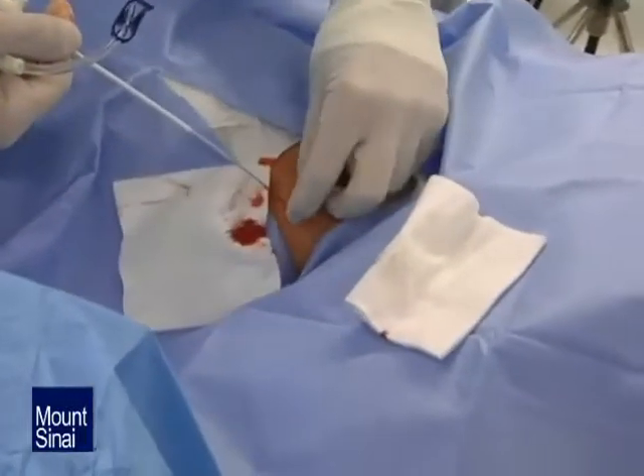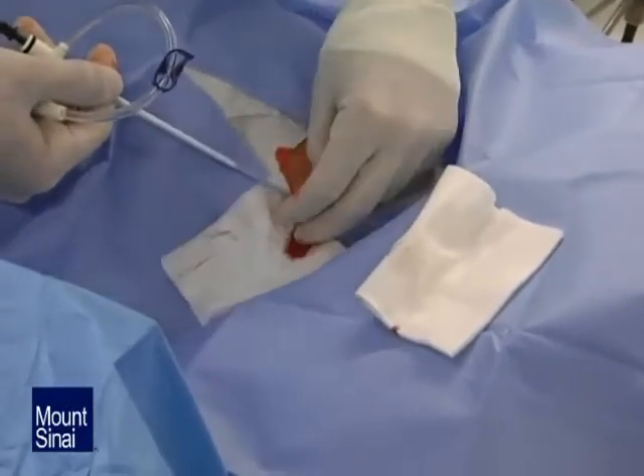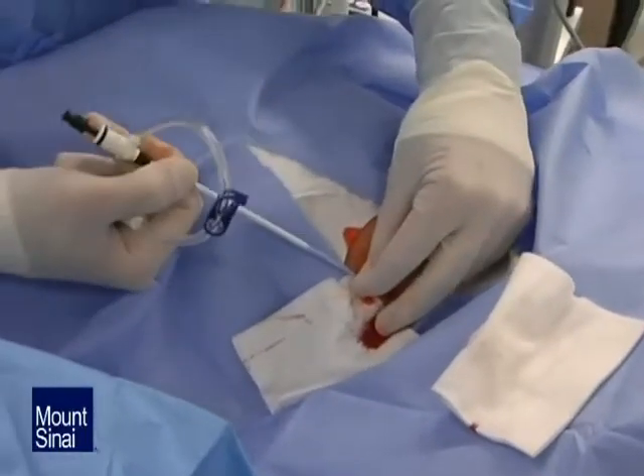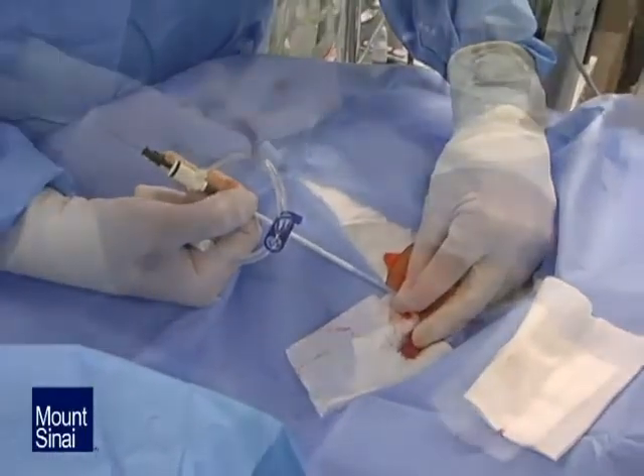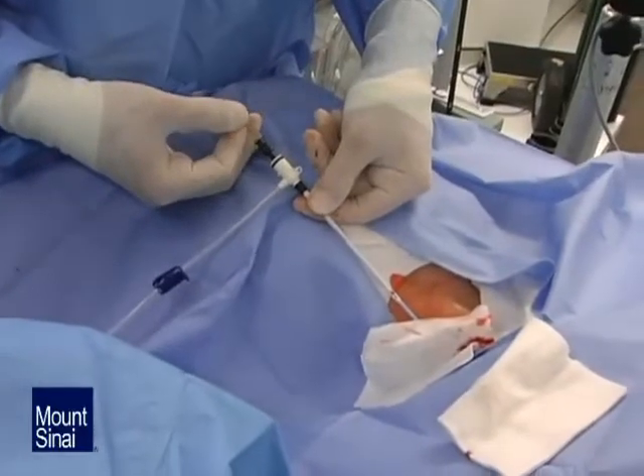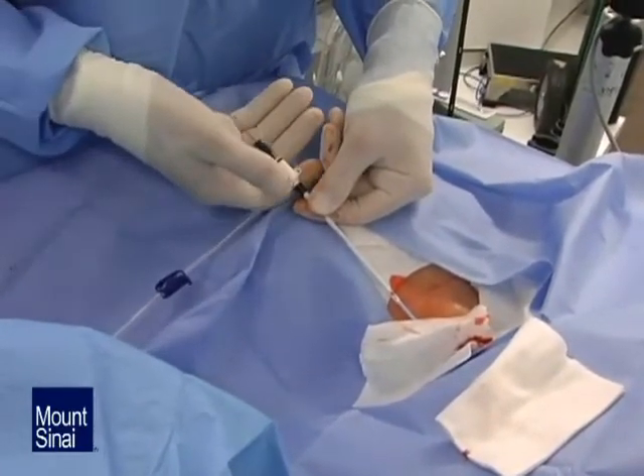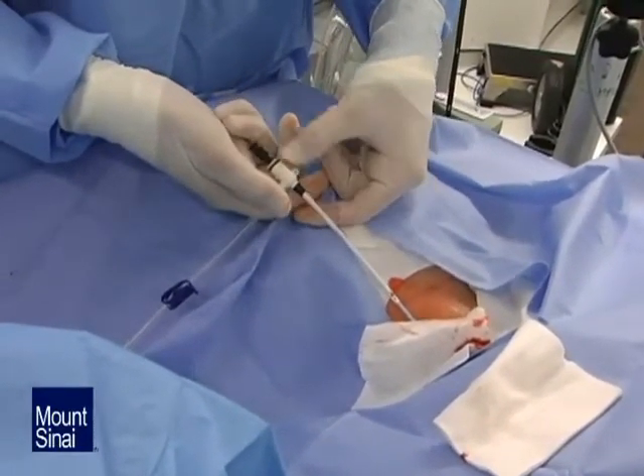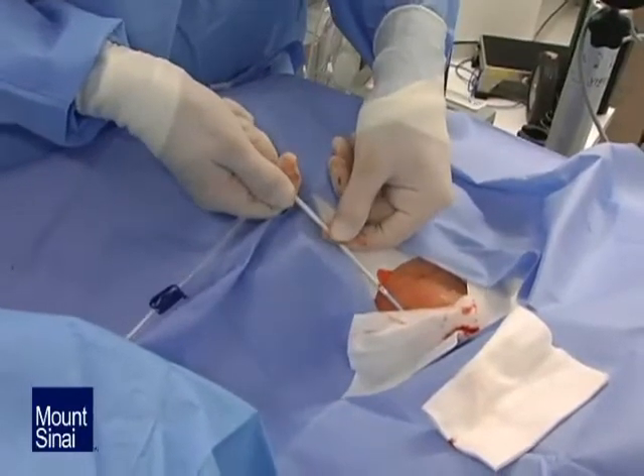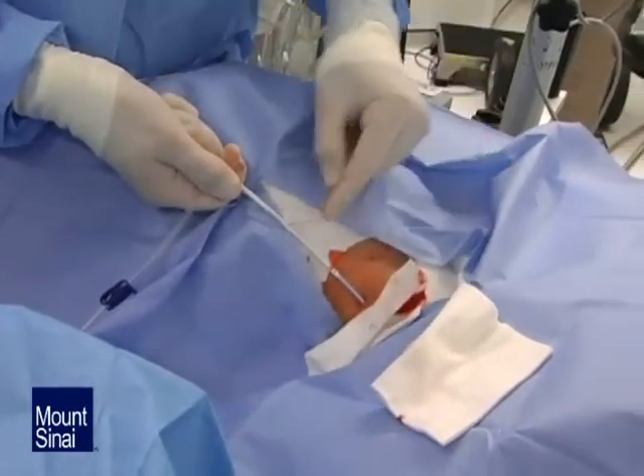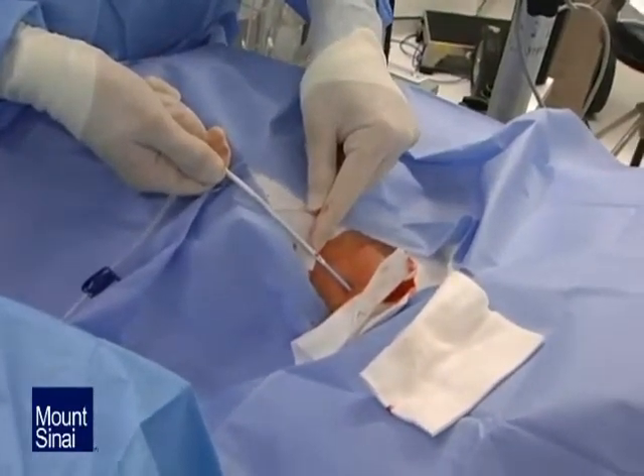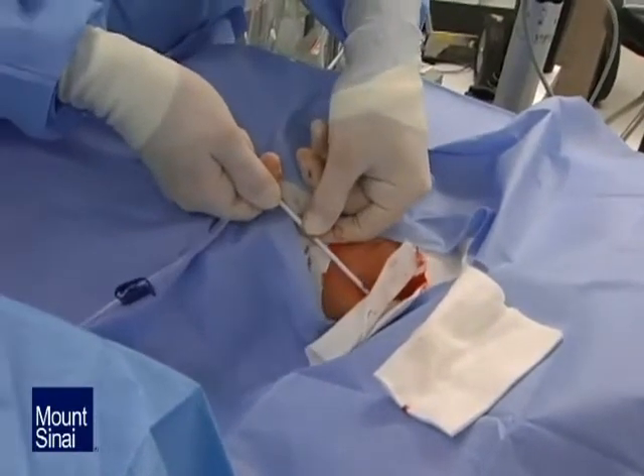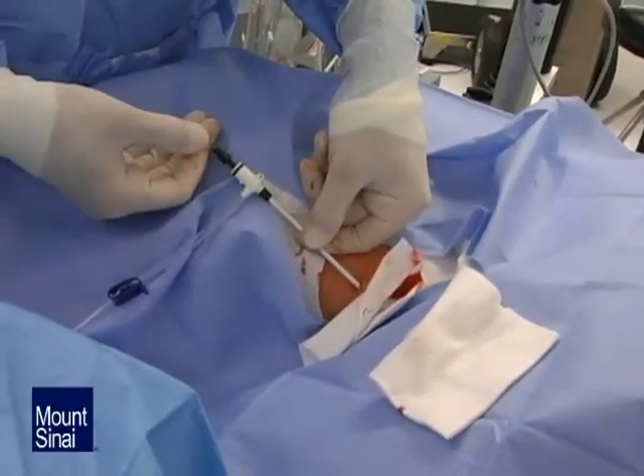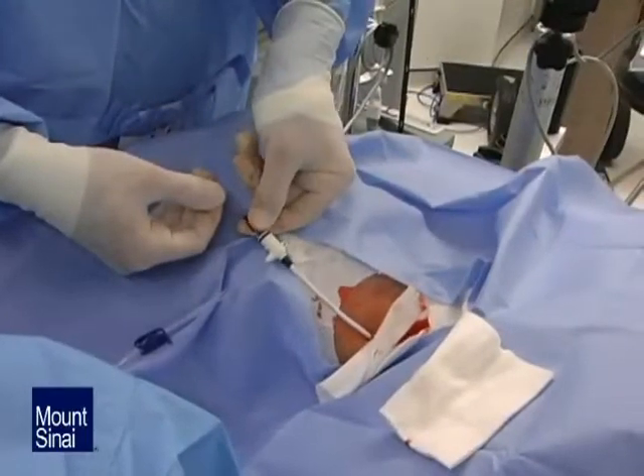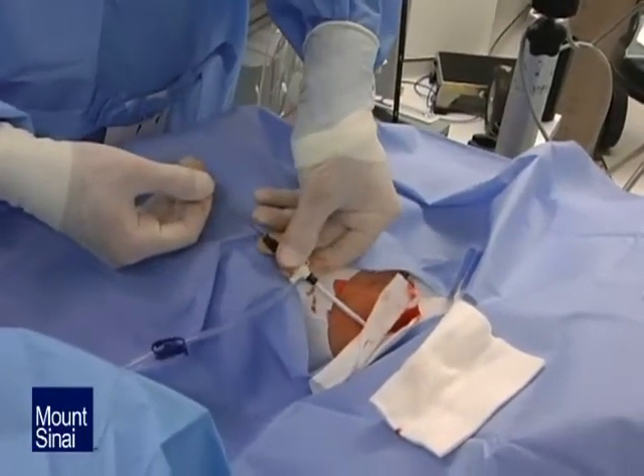The introducer and dilator assembly are then placed over the wire. If necessary, withdraw the wire until it emerges from the top of the dilator. In the Seldinger technique, it is imperative that the operator never loses control of the wire. Advance the entire assembly along with the wire to a depth of about 1/3 the length of the dilator. If the wire moves easily and is not bent or kinked, it is confirmed that the dilator is following the wire's trajectory. Next, brace the wire and advance the dilator and introducer half the remaining length.